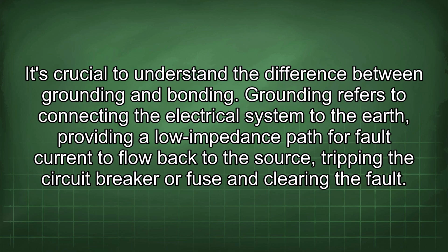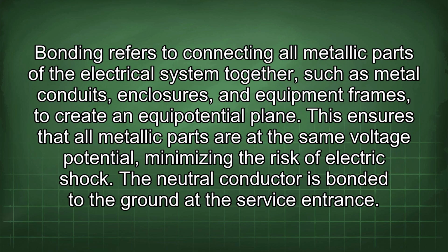It's crucial to understand the difference between grounding and bonding. Grounding refers to connecting the electrical system to the earth, providing a low impedance path for fault current to flow back to the source, tripping the circuit breaker or fuse and clearing the fault. Bonding refers to connecting all metallic parts of the electrical system together, such as metal conduits, enclosures, and equipment frames, to create an equipotential plane. This ensures that all metallic parts are at the same voltage potential, minimizing the risk of electric shock.